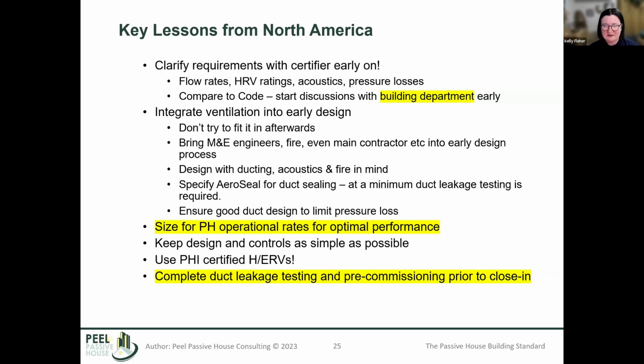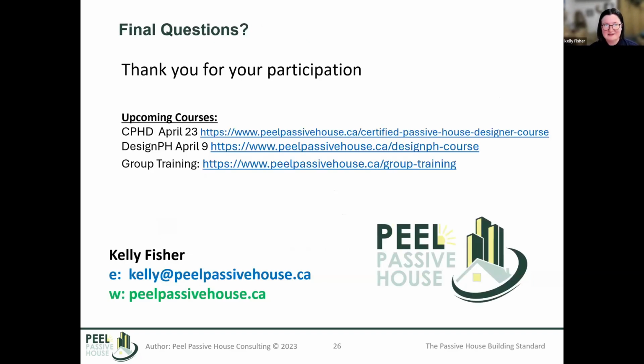And yeah, complete your duct leakage testing as a pre-commissioning step, so before you cover everything up, making sure that you're doing your leakage testing or your sealing at that point. I like some of Michael's examples where construction was still very much underway and they're sealing the ductwork, which is exactly what we want to see. You don't want to wait until you've got drywall in and everything covered up so that you can't access it. So that's it for me. So back to Ken. I think we've got a bit of a Q&A.